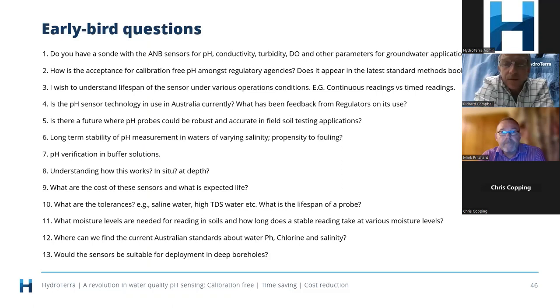In summary, the turbidity side of things isn't currently an option, and DO's not currently an option either. So pH, temperature and conductivity. If you do need all of those in one measurement sonde, we can interface it back at HydroTerra to have multiple inputs coming into telemetry to do that. But you may get to the point where you run out of space down a conventional monitoring well, as the diameter can get too big, so it depends on the diameter of your groundwater well.